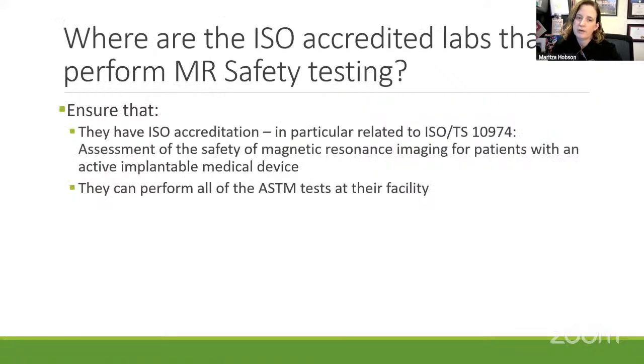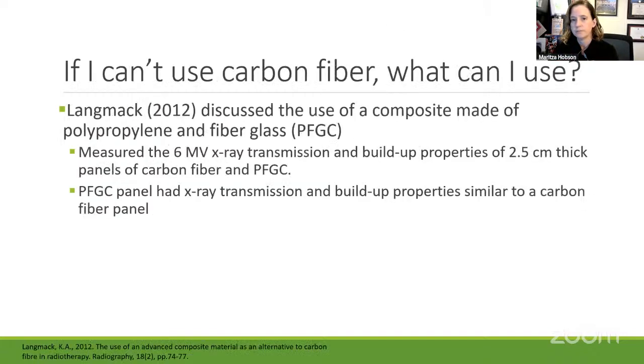Okay, where are the ISO accredited labs that perform MR safety testing? There are a few facilities in the US that provide MR safety testing. You need to make sure that they have ISO accreditation, particularly related to ISO/TS 10974. That's the number for what we need for MR safety testing, and that they can perform all the ASTM tests at their facility with the size of the RT immobilization device or accessory you would like to be tested, and hopefully as close to your MR system values as shown in Table 3.